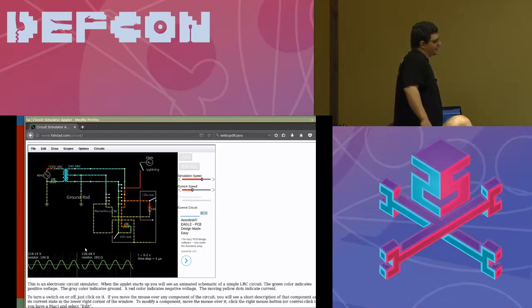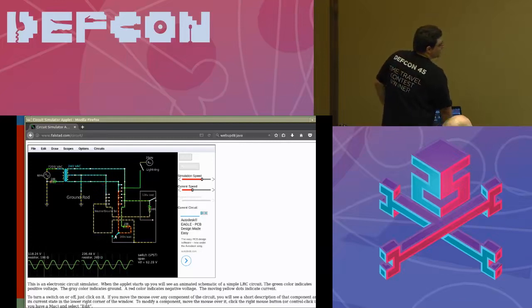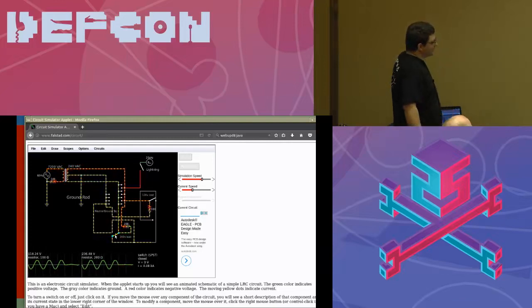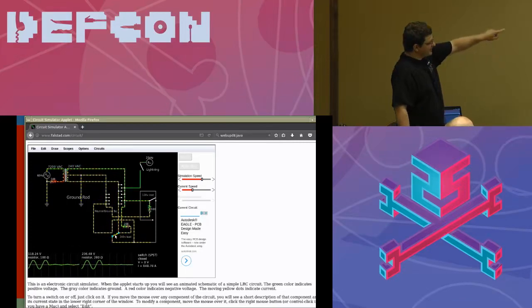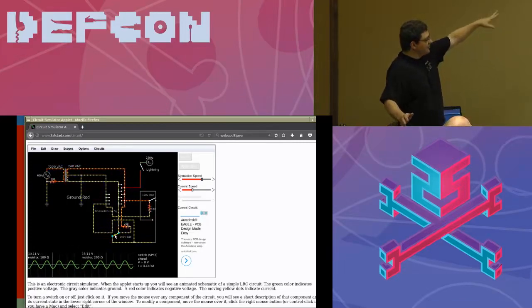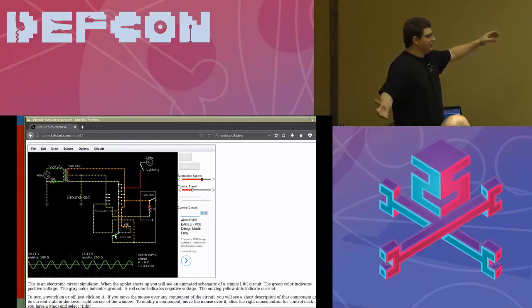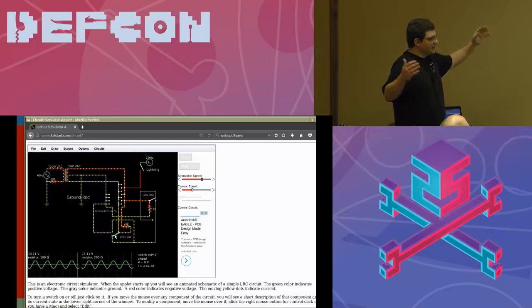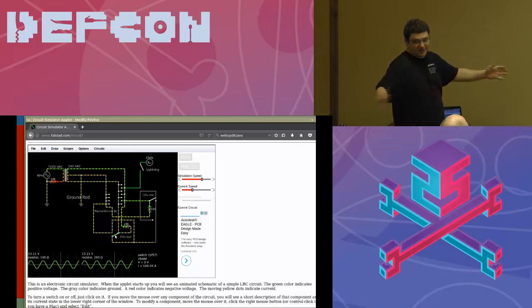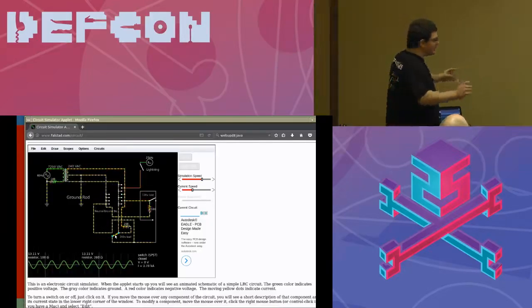So if we have a ground fault, watch this thing completely negate my point. Now we have a ground fault here. Now the safety ground is carrying current, and that's the only time it does. But if you notice, the ground rod is not doing anything. It's not doing anything under fault conditions, it's not doing anything under normal conditions. It really doesn't, if you disconnected it, not much would happen. It doesn't do a whole lot.